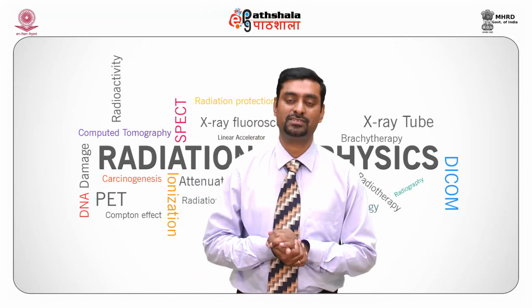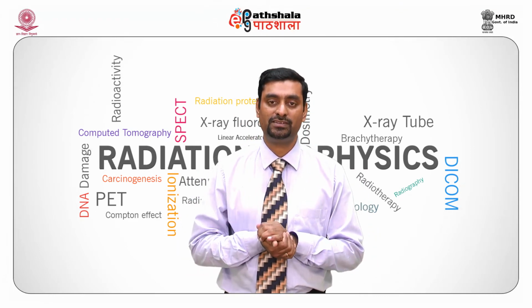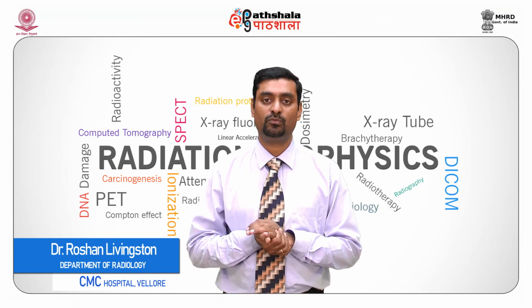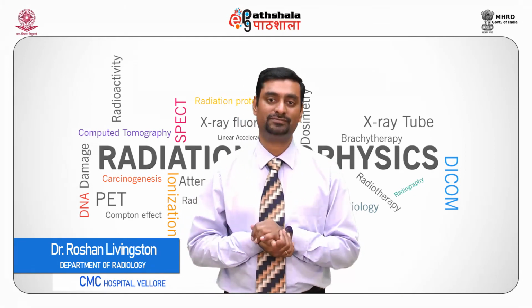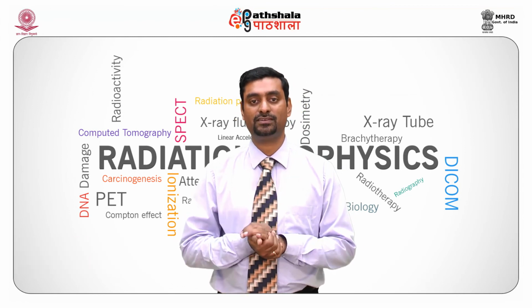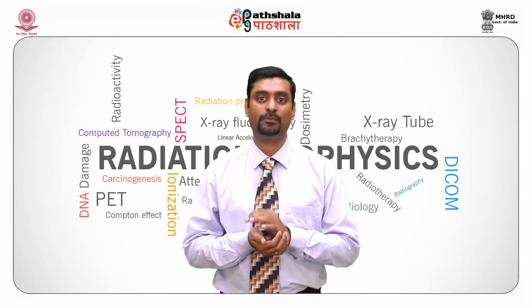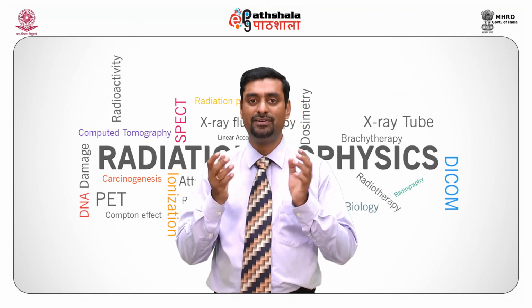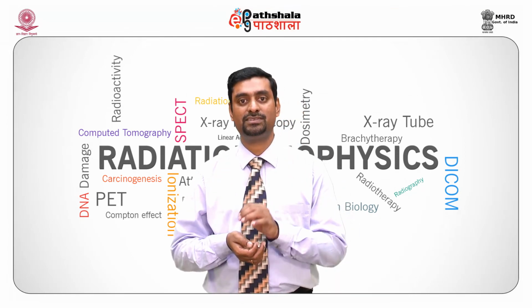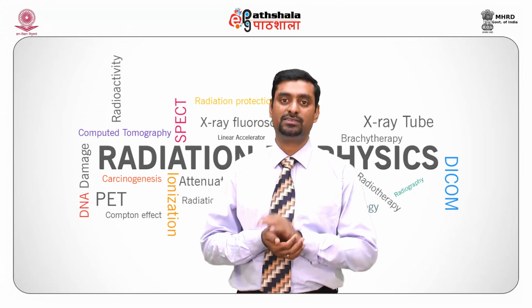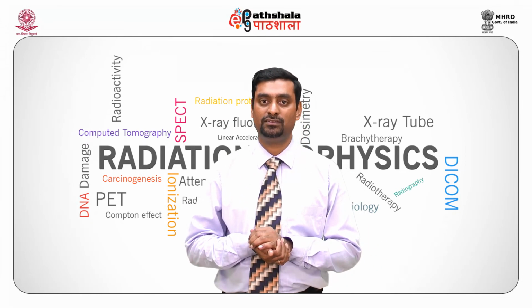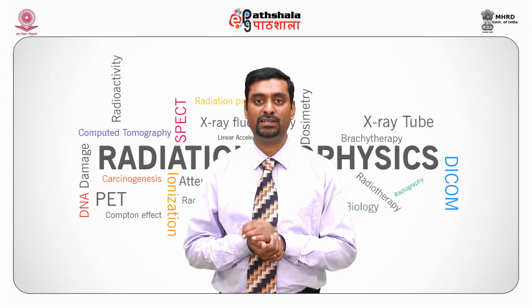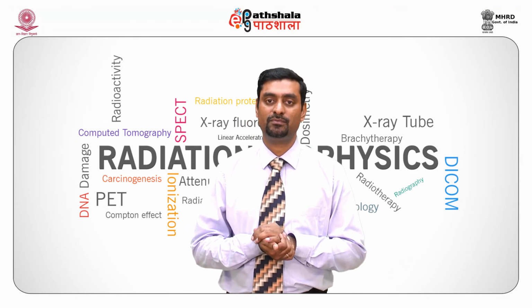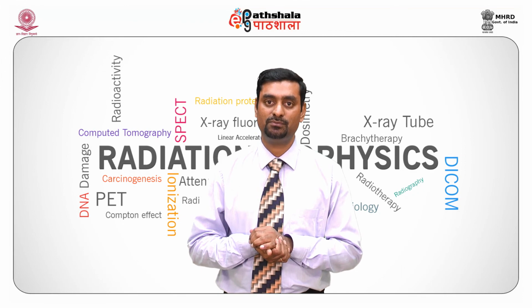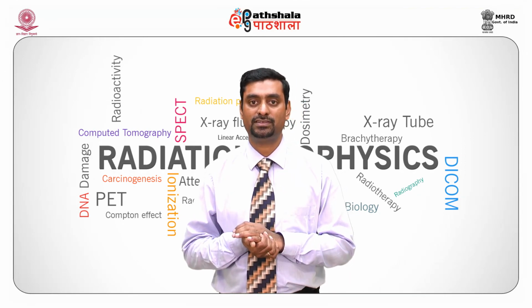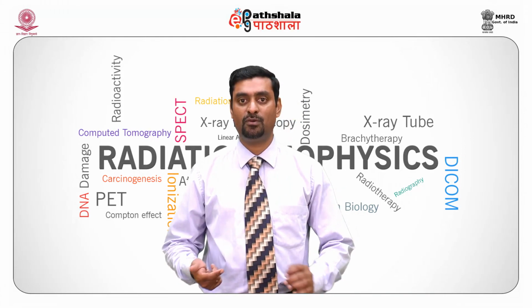The computed radiography system uses an image phosphor plate which has barium fluorobromide doped with europium-2+. When X-rays fall on that, this europium-2+ becomes europium-3+. When this cassette is fed into the reader, the laser present inside the CR reader stimulates the europium-3+ to form europium-2+. By the way, it gives off small light photons which are useful for imaging purposes. This light is absorbed by a photomultiplier tube for image formation.